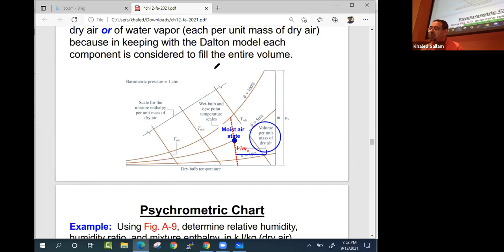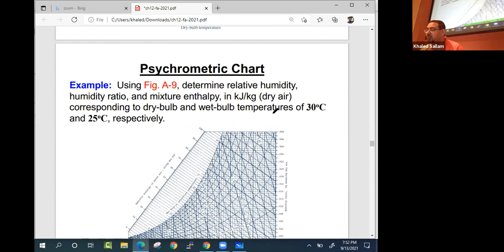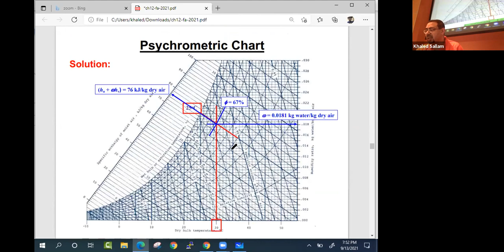Here's an example: determine the relative humidity, humidity ratio, and mixture enthalpy in kilojoules per kilogram dry air using a dry bulb and wet bulb of 30 and 25. So go to 25 and up until you hit 100%, then go at constant H until you strike here between dry and wet. Wet is lower than dry because there's room for the air to get more water and cool down when it does this.